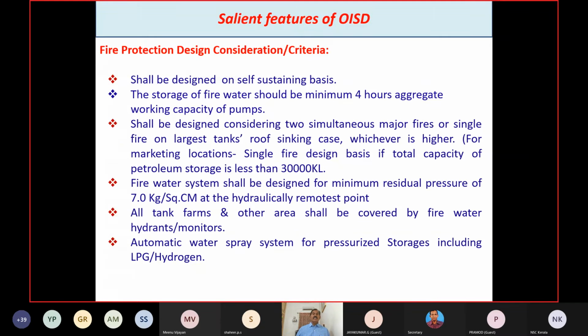See, the fire protection design consideration and criteria. So actually the fire protection facility for any factory should be decided based on the nature of the industry and the risk involved in the industry. Based on this, the fire water storage and the capacity of the pump should be determined. The storage of fire water should be minimum 4 hours aggregate working capacity of pumps, and it shall be designed considering 2 simultaneous major fires or a single fire on the largest tank, that is the roof sinking case, whichever is higher. For marketing locations like POL, single fire design basis if the total capacity of petroleum storage is less than 30,000 KL. If it is more than that, a double contingency plan should be adopted.